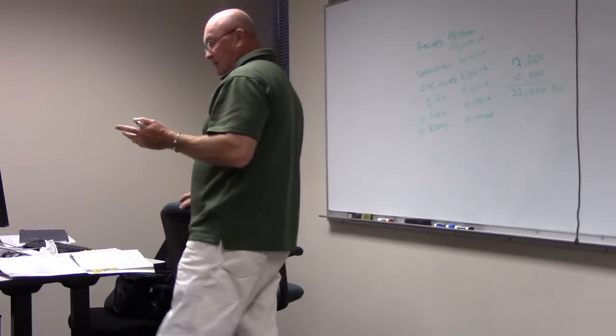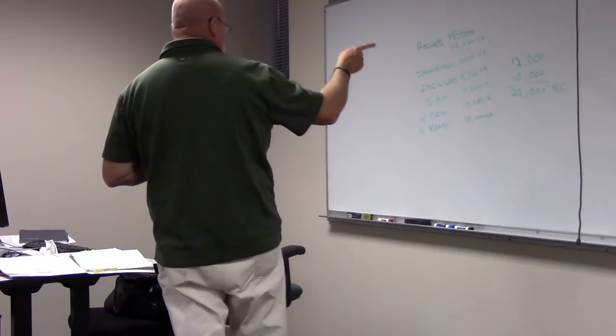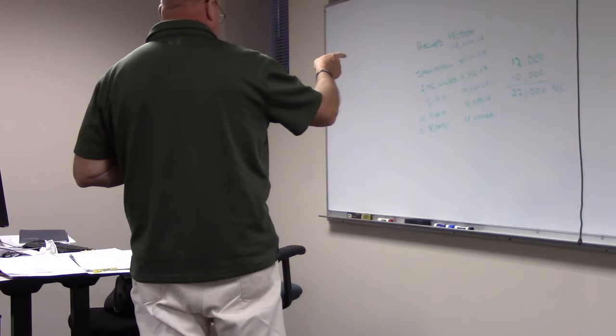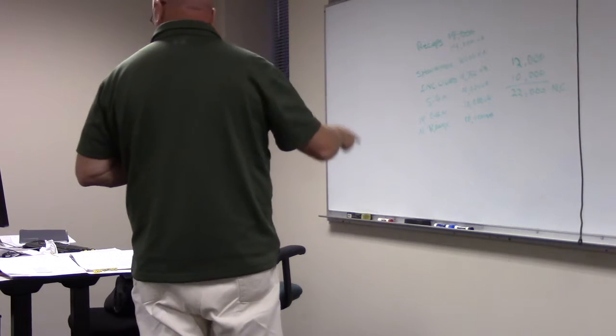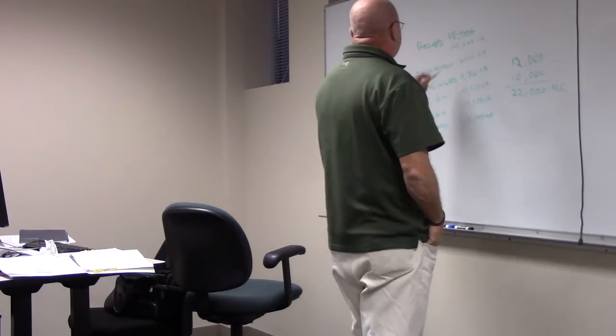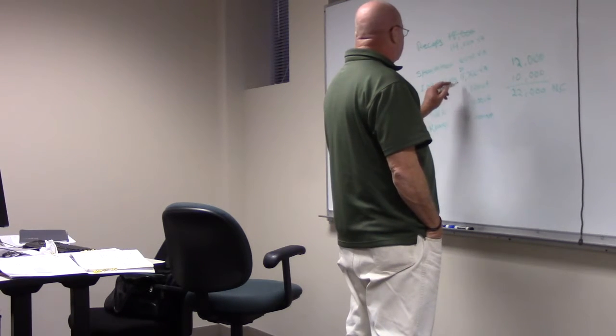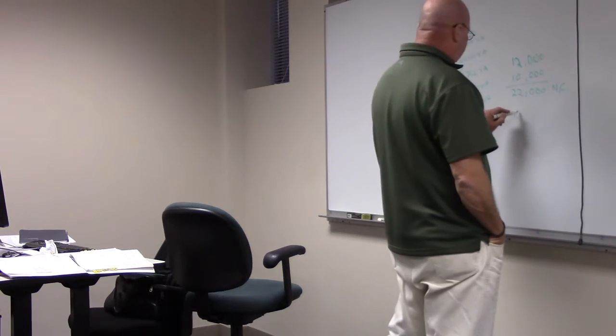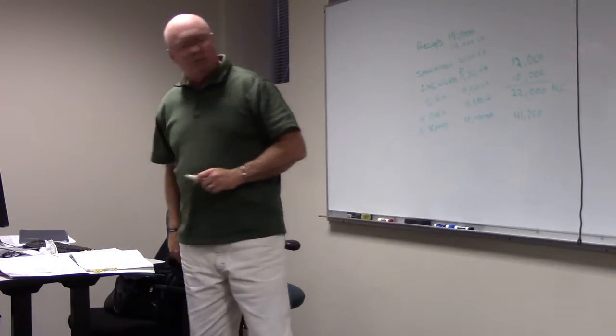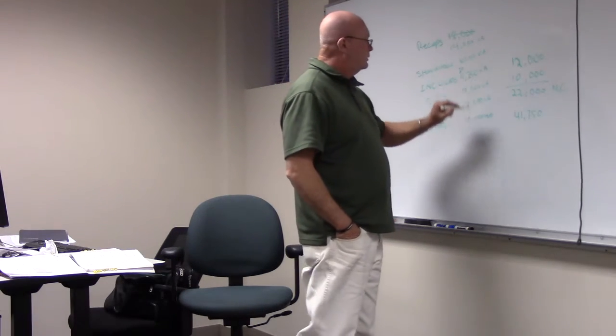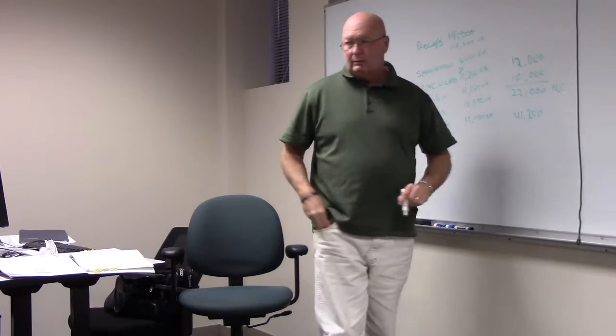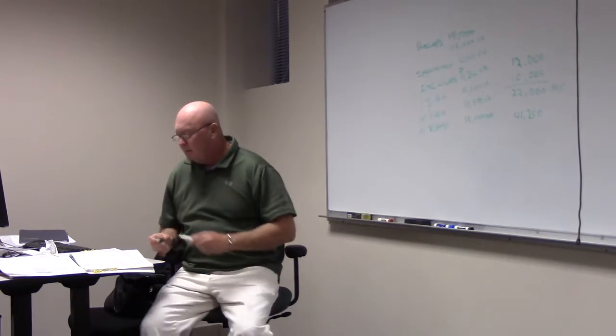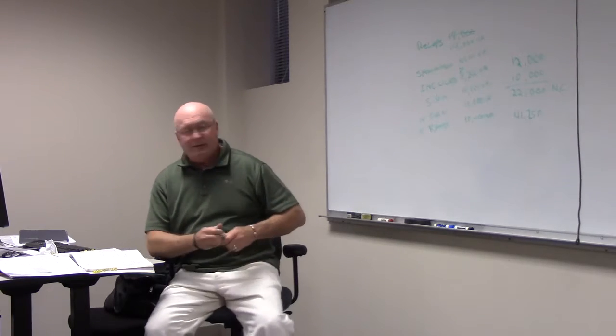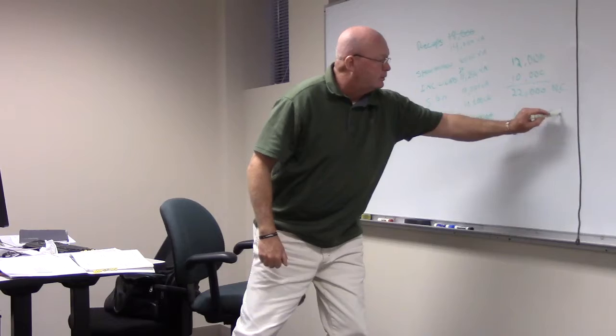So that means the rest of our load, I think our receptacles, because they actually said our receptacles were what? Continuous. Is it going to be continuous? Yeah, right? Incandescent lights and the signs. We're going to light all those up then. So that's 20, 30, that's 41,750. That's at 2. 41,250, right? Okay. 41,250, that's our continuous load. Go ahead and do it, so we can be on the same page.